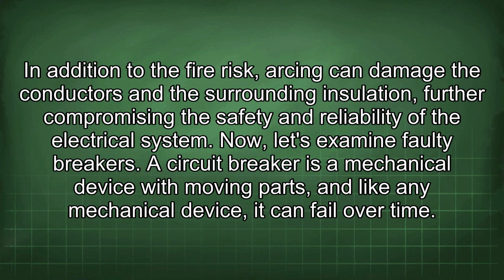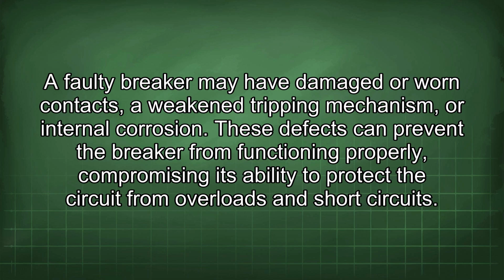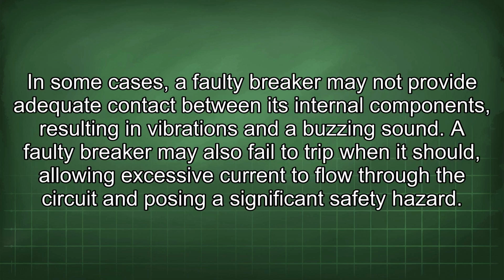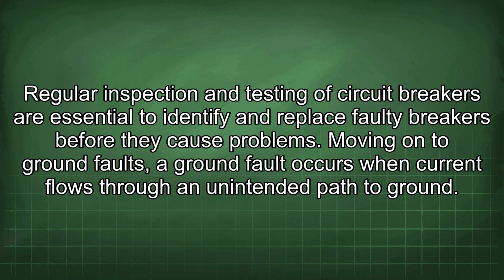Now let's examine faulty breakers. A circuit breaker is a mechanical device with moving parts, and like any mechanical device, it can fail over time. A faulty breaker may have damaged or worn contacts, a weakened tripping mechanism, or internal corrosion. These defects can prevent the breaker from functioning properly, compromising its ability to protect the circuit from overloads and short circuits. In some cases, a faulty breaker may not provide adequate contact between its internal components, resulting in vibrations and a buzzing sound. A faulty breaker may also fail to trip when it should, allowing excessive current to flow through the circuit and posing a significant safety hazard. Regular inspection and testing of circuit breakers are essential to identify and replace faulty breakers before they cause problems.